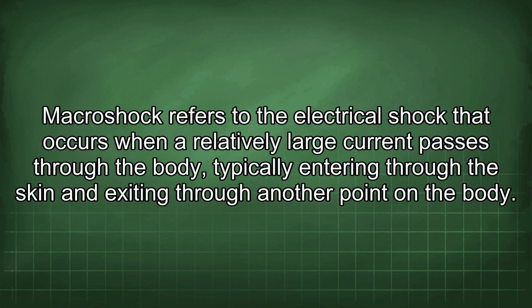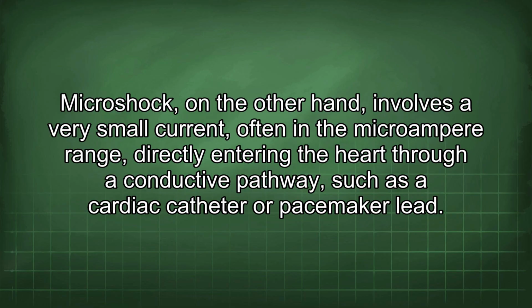Macroshock refers to the electrical shock that occurs when a relatively large current passes through the body, typically entering through the skin and exiting through another point on the body. Microshock, on the other hand, involves a very small current, often in the microampere range, directly entering the heart through a conductive pathway, such as a cardiac catheter or pacemaker lead.